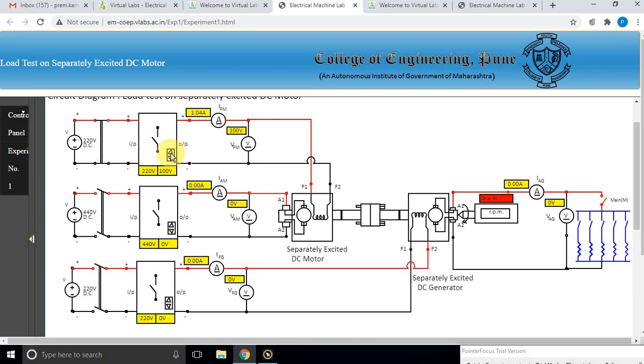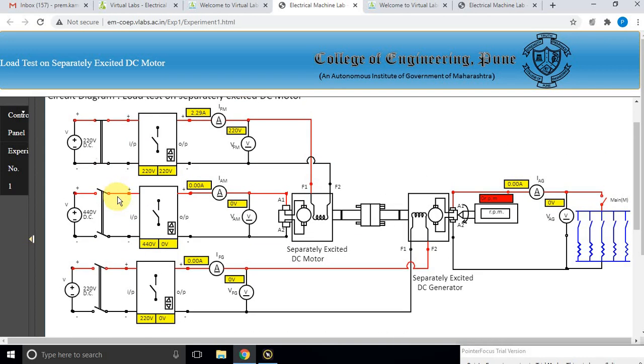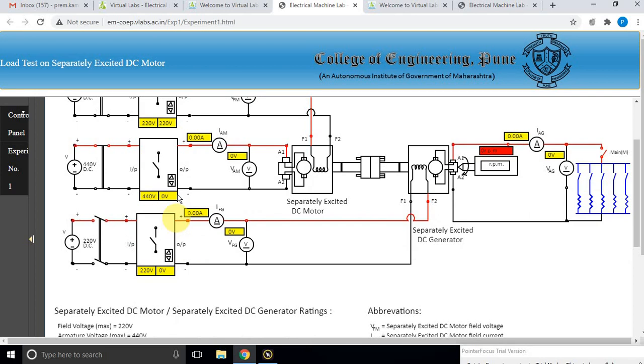The field excitation voltage is fixed at 220 volts — the rating of the field excitation is 220V, 2.3 amps. Adjust and fix it at 220 volts. After that, you need to rotate the separately excited DC motor at rated speed. Close this switch, which controls the armature voltage, and adjust the armature voltage using this button.